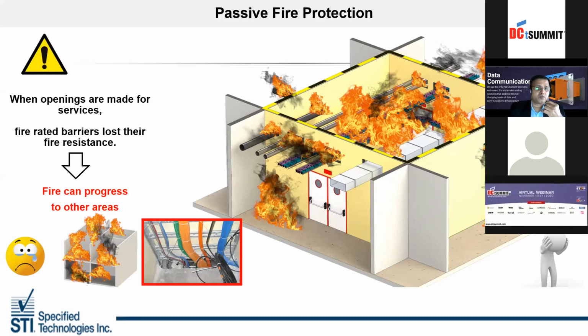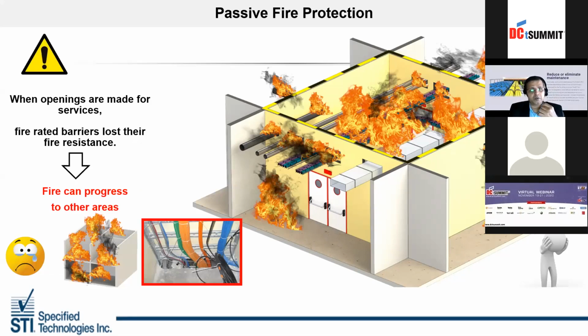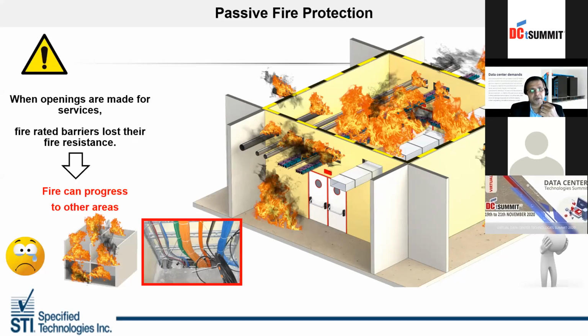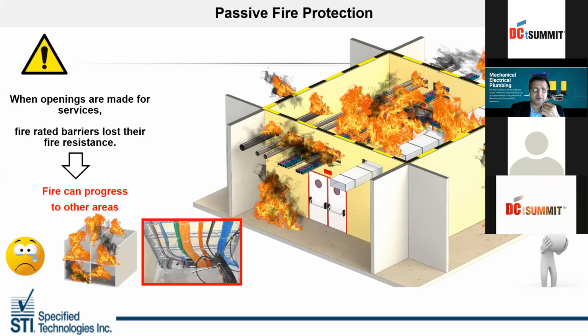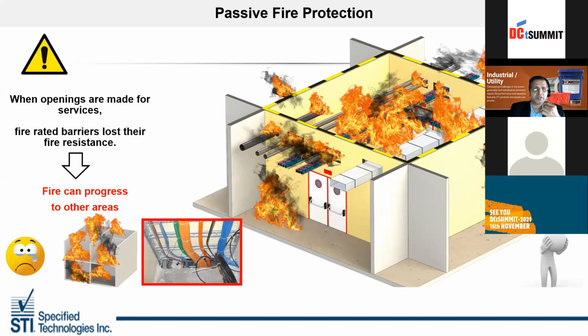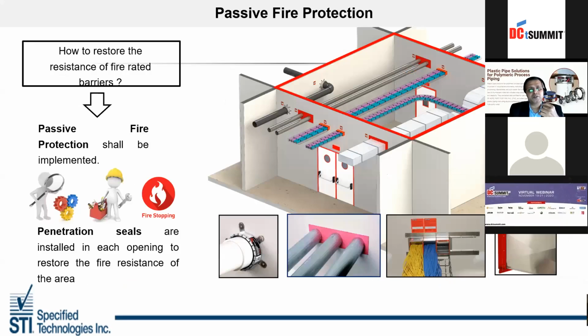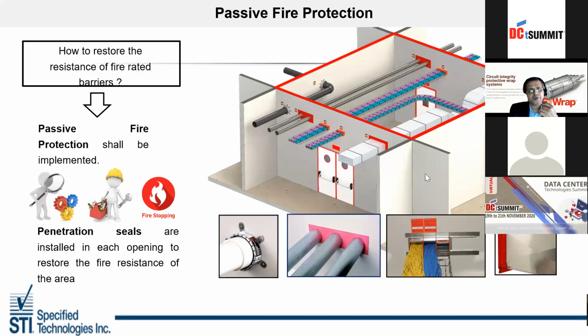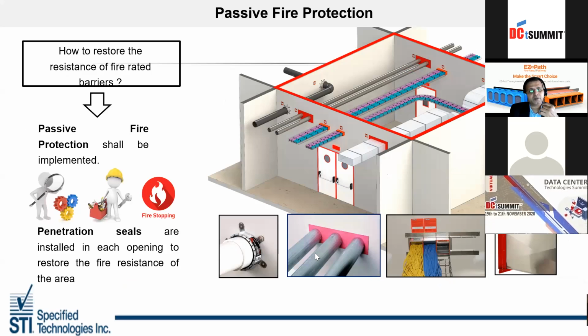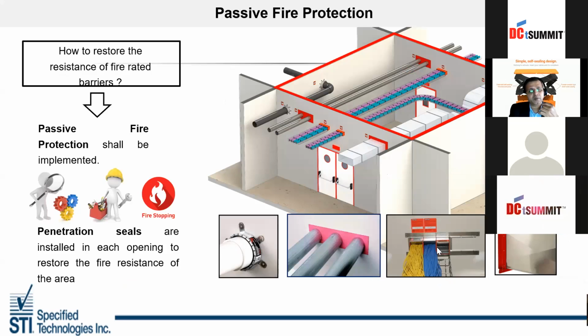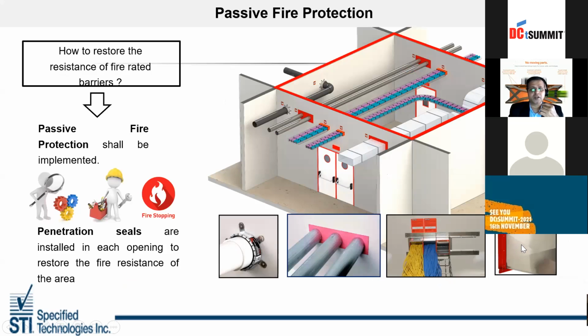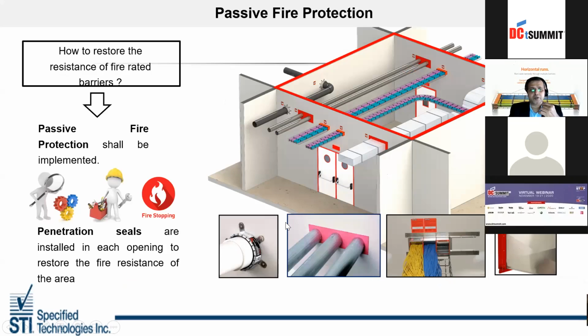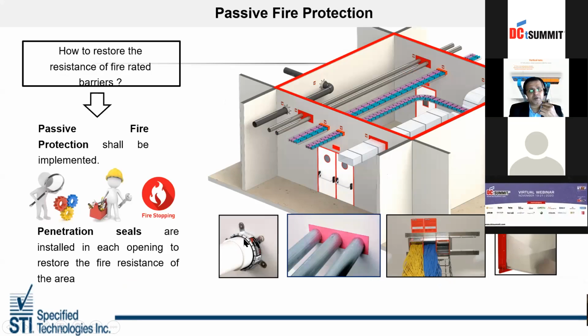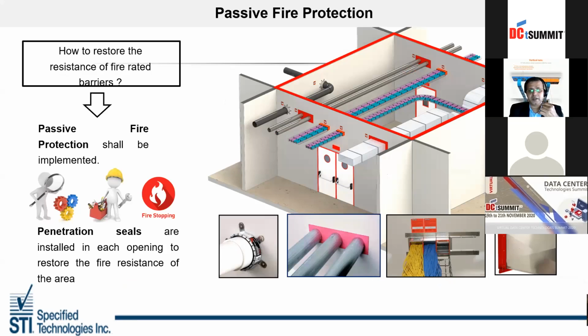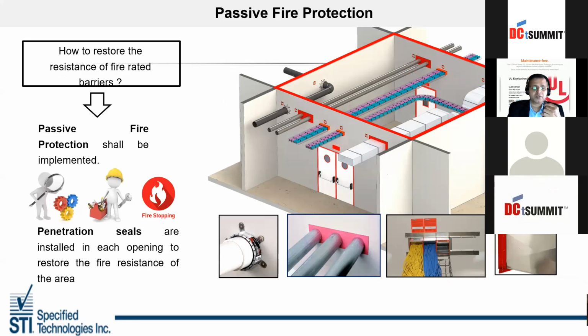The office cannot be operational for, say, a month or two months, depending upon the scenarios and the jurisdictions, where you need to prove that the fire has happened and you need to move all your office items to a new place and start up new. What happens if you have sealed all the penetrations with proper fire stopping systems? Whatever is red in this building: the metallic pipe has been sealed with endothermic sealant. The cables and cable trays are protected with a fire stopping product. The ducts have been protected with an equal fire stopping product. The plumbing pipes and the electrical cable trays, the most important parts in any building, have to be sealed with proper fire stopping systems.